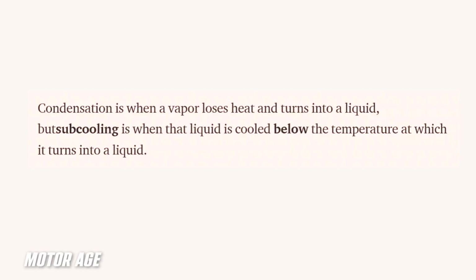So as you can see here, condensation occurs when a vapor loses heat and turns into a liquid. But subcooling is when that liquid is cooled below the temperature at which it turns into a liquid. So what I mean by this, as pressurized, hot, high-pressure gas leaves the compressor and heads through the condenser, it sheds its heat, right, British thermal units, to the air, to the atmosphere that blows across those condenser fins through that process of convection. When the gas or the gaseous refrigerant becomes liquefied refrigerant, that's condensation. However, when that temperature of that liquid refrigerant begins to drop afterwards, that is known as subcooling.